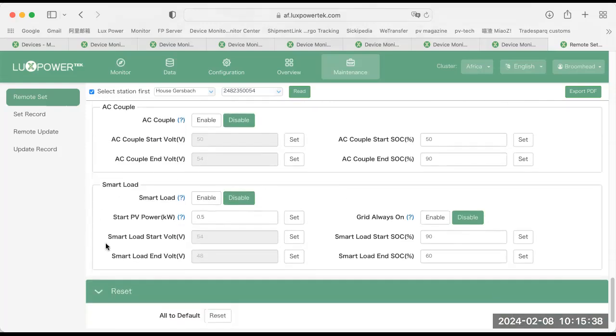All right, and then here's the cool one. You know, the other inverter manufacturer called it an auxiliary port. Ours is a smart load port, so we can put power out if you enable it. It simply means that you can set your start PV power, and you can also set the battery. In other words, when the battery is between this SOC range, then it will use the smart load port. It'll put out power, but only in load shedding mode. Sorry, when the grid is on, it still puts out power through that port. But if you do not want to use grid to take it, just disable this one, remember?